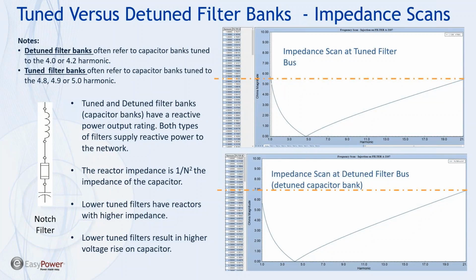So here on this slide, I'm showing 2 impedance scans. The top impedance scan is for a tuned filter. Basically, the impedance drops down to a low value at the tuning point, which in this case is 4.7, and then we rise back up in impedance as we go up in frequency. So on the left axis, we have ohms. On the right axis, we have harmonic number. The lower impedance scan here is a detuned filter. Really, the impedance scans look the same if you think about it. The only difference is the low frequency point here. In this case, it's 4.2.